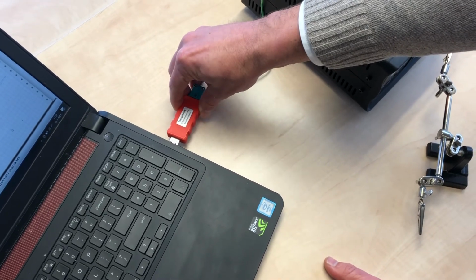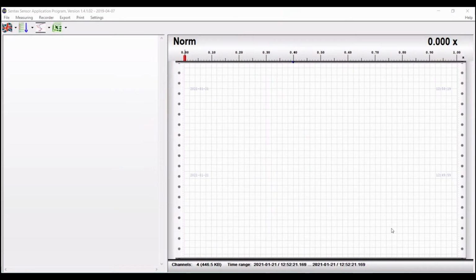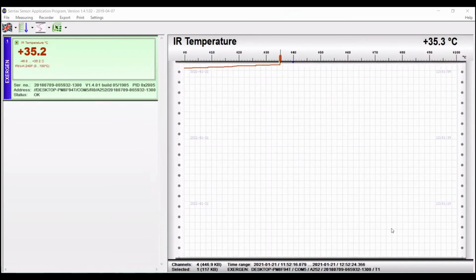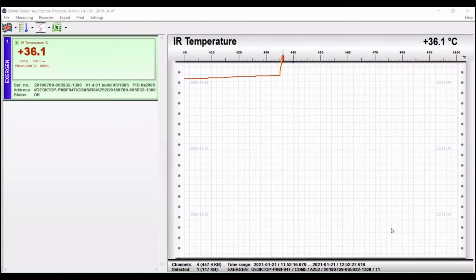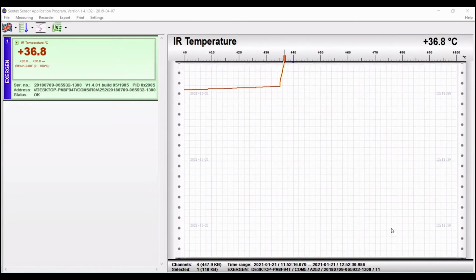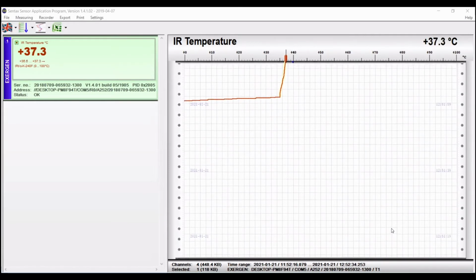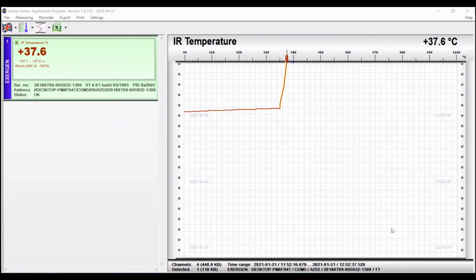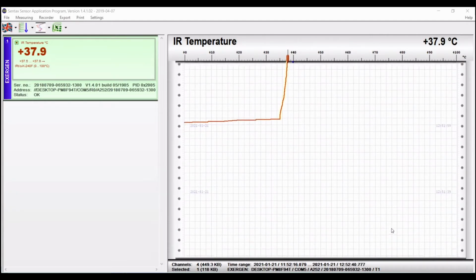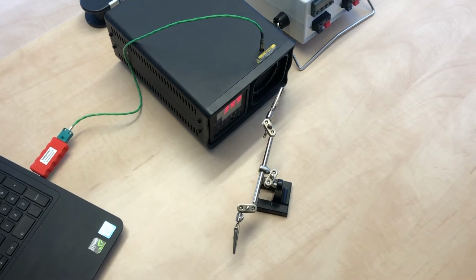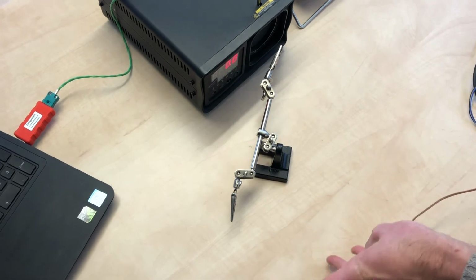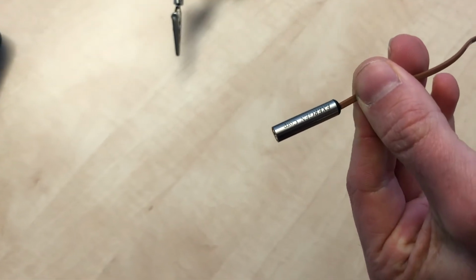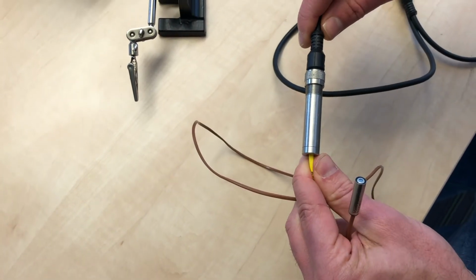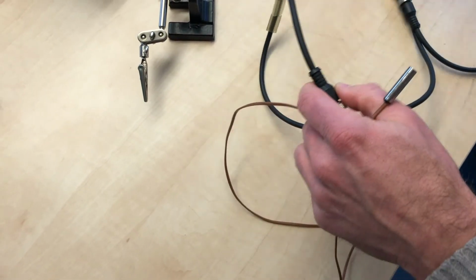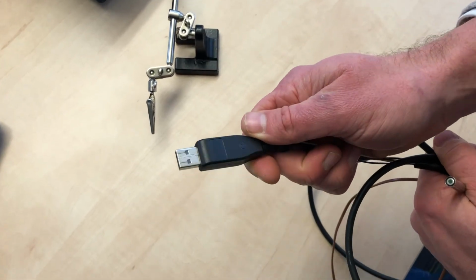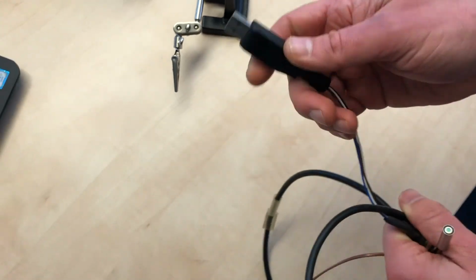plug in the stick, the USB stick, into the laptop, and you immediately see that the software recognizes the reference sensor. What you also see is that this is a contact sensor. It came from a somewhat colder environment, so this one takes some time to adjust. In practice, you also need to give your reference sensor time to adjust and take the temperature of your target. For this demonstration, I will use the Micro IRtc connected to the AutoSmart. I've already plugged in the M12 connector, and in this case, instead of the 4-wire output, I have the USB stick.